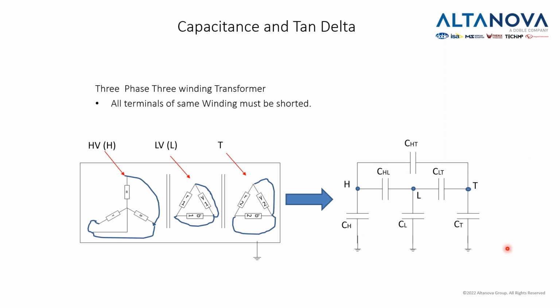If we have tertiary, of course, we have more capacitances which we need to measure: high voltage to ground, low voltage to ground, and tertiary to ground, and everything in between. The good thing about this test is that we have, let's say, a better resolution, in the sense that if we have an issue only with one insulation, let's say low voltage to ground, we will see that, because in another test, which we'll see in the end, the DC test, we are just measuring one resistance. Here we measure all kinds of insulation. When I say all kinds, I mean insulations between different points of voltage.